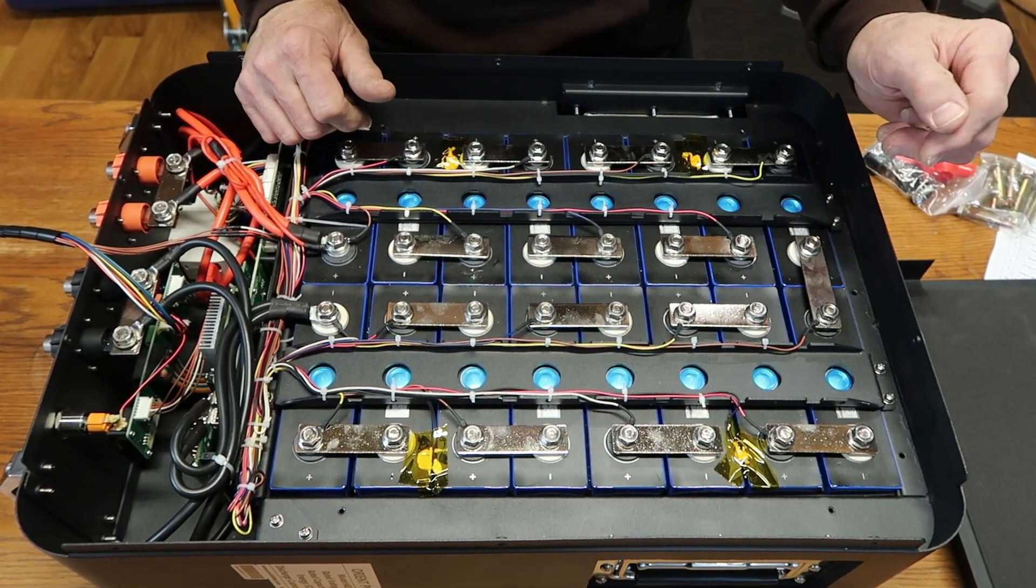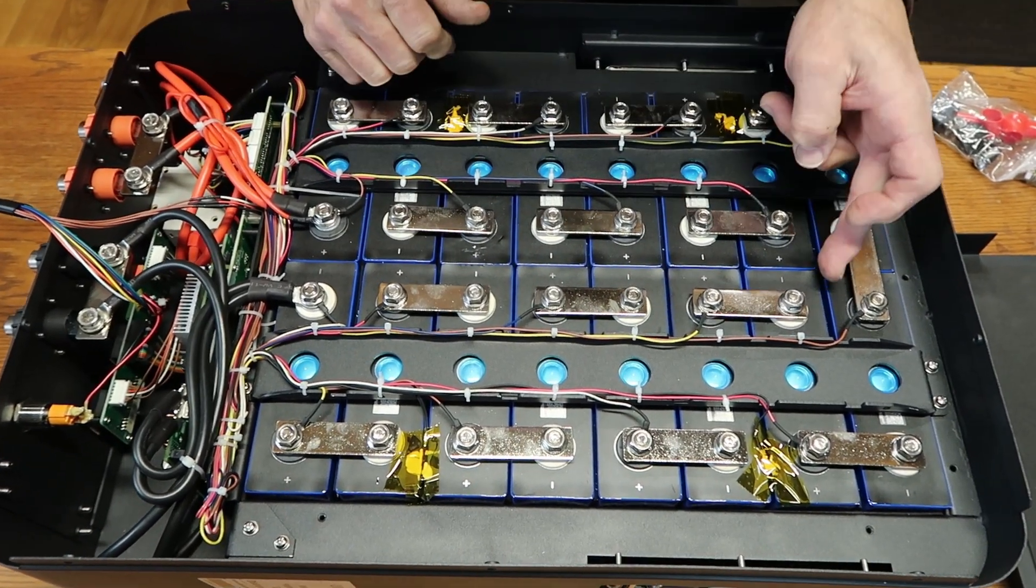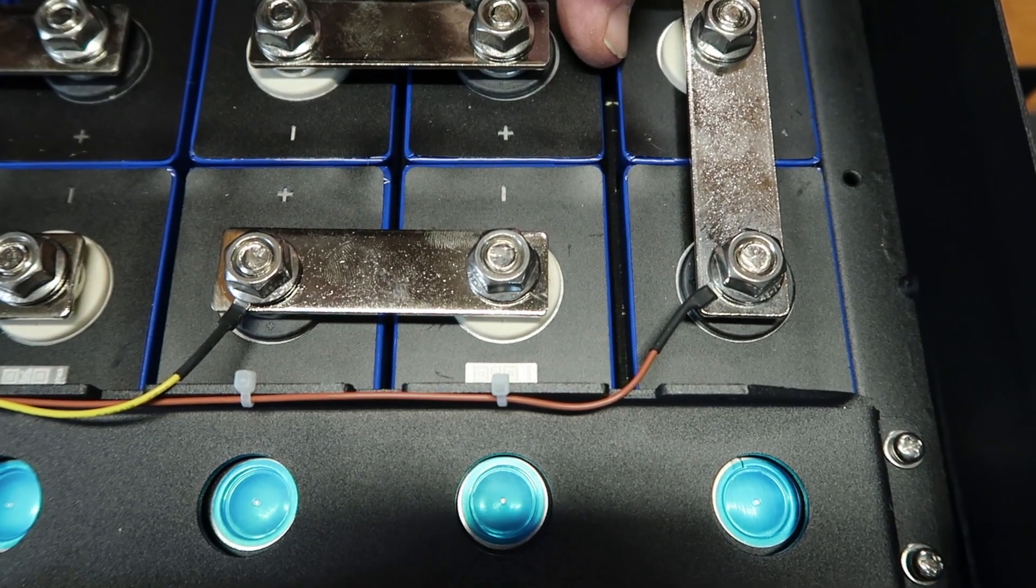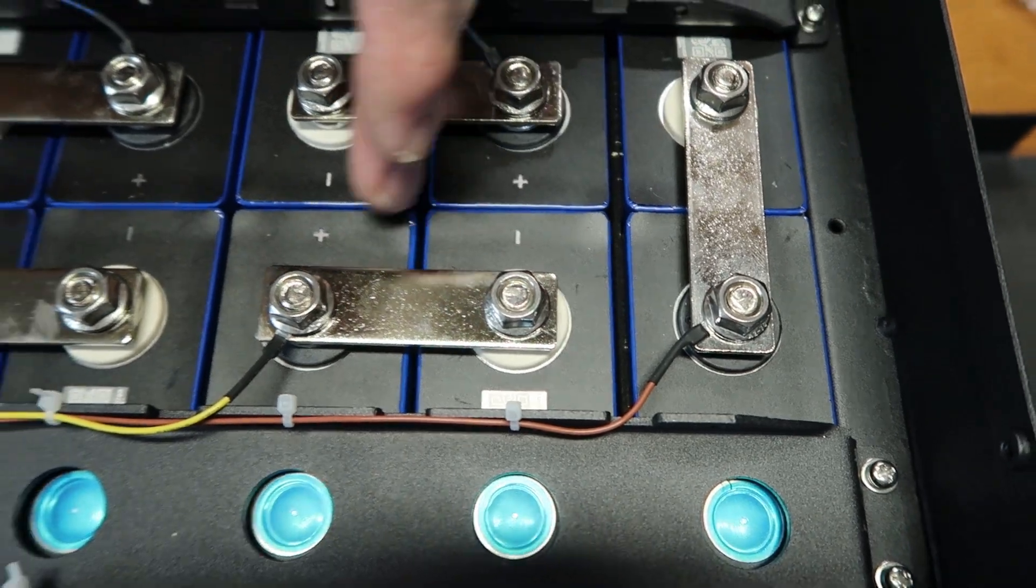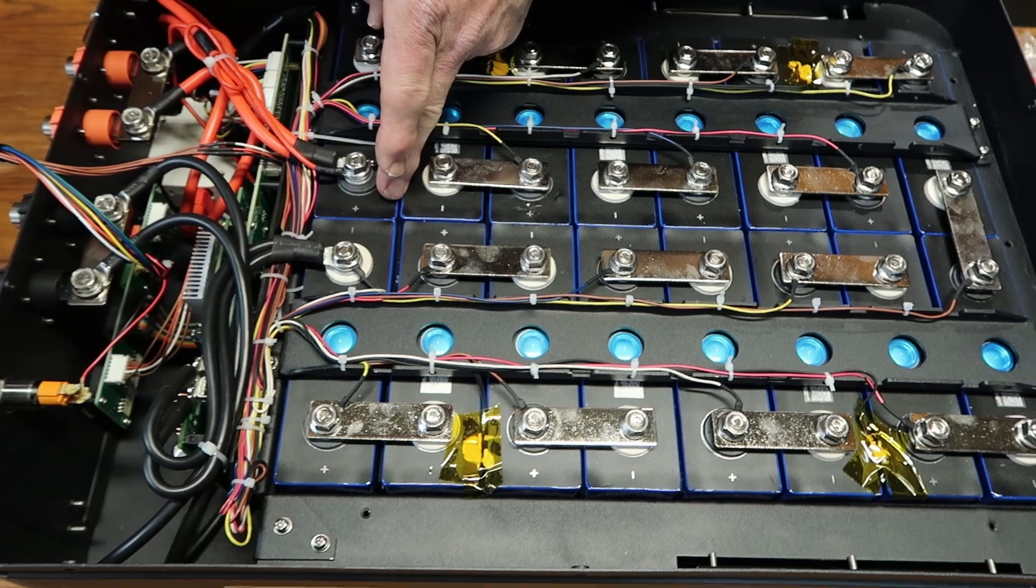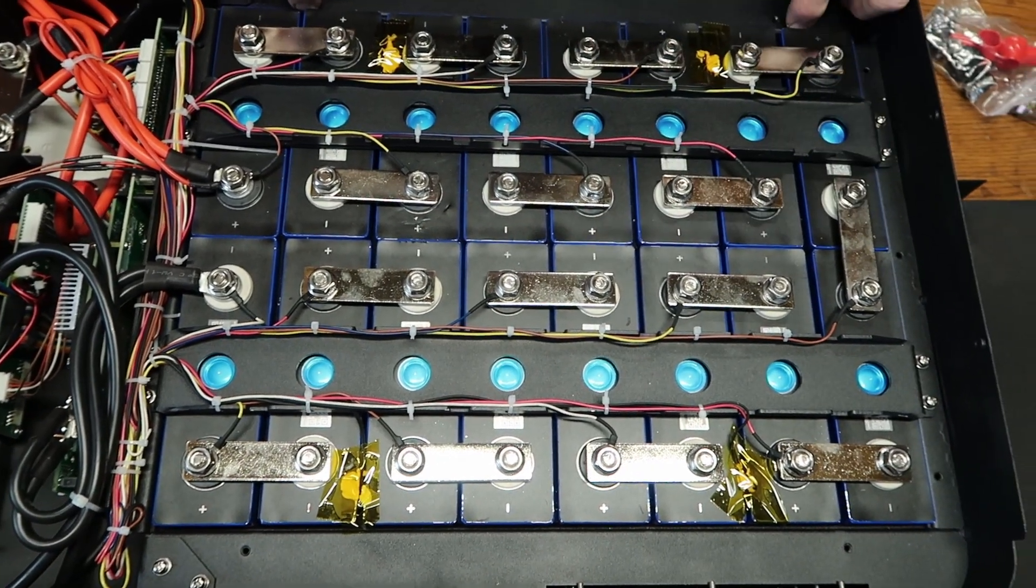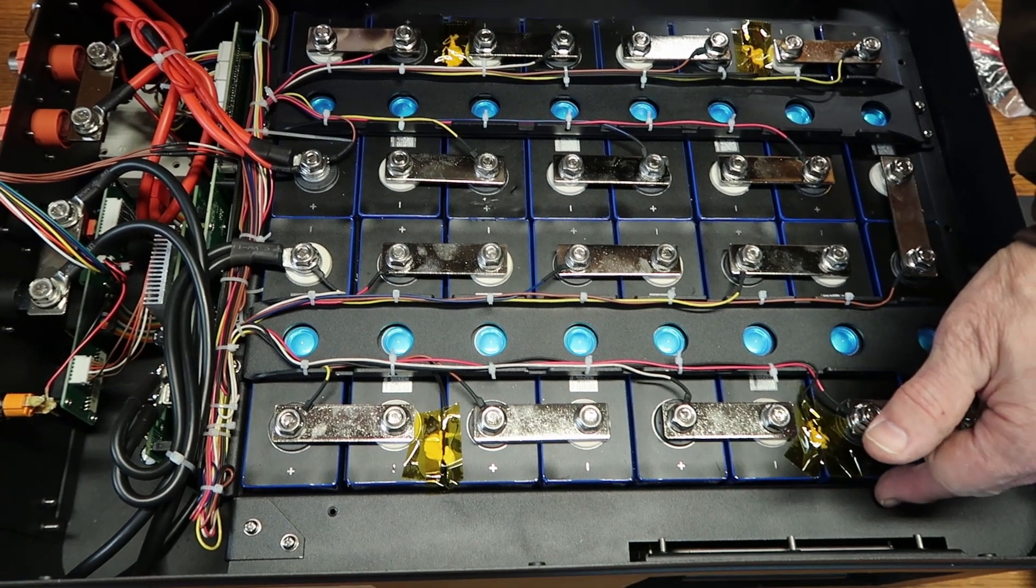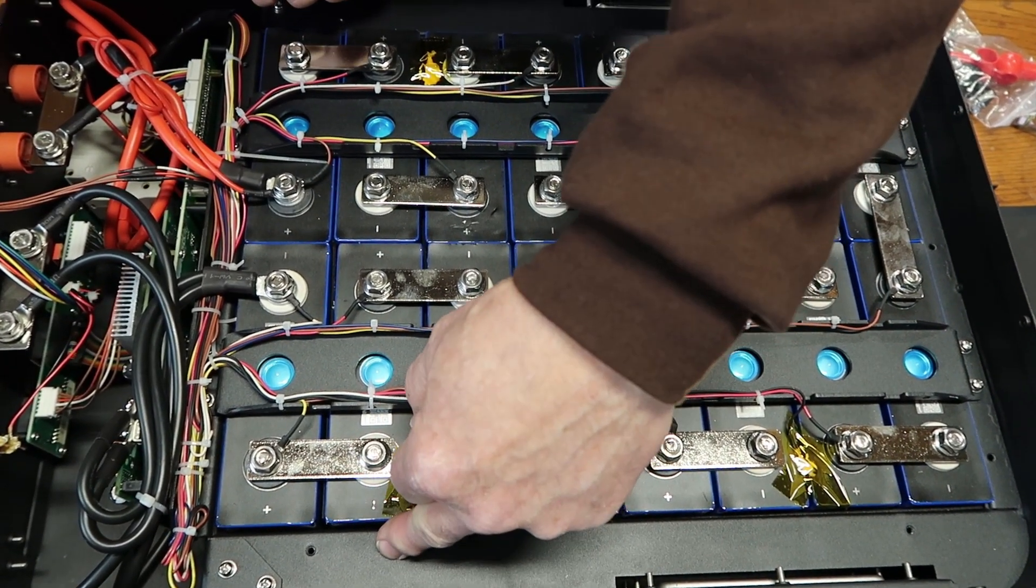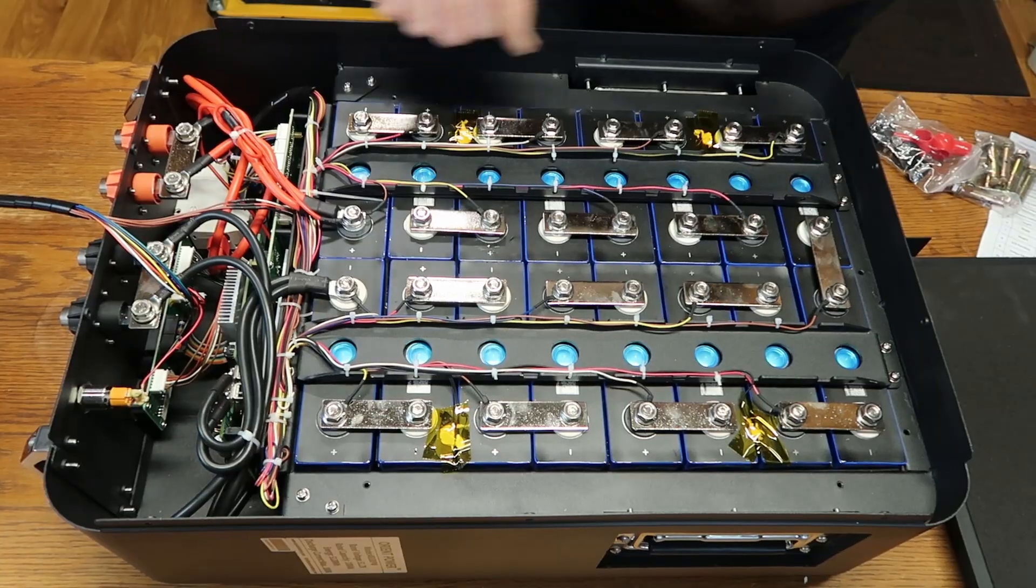We did notice that probably to help from any kind of rubbing with any expansion on the cells, in between these rows we do find the tape foam that they usually tape onto the sides. Each one we did check down, they all have the tape. There is foam along the side. So we're protected along the sides from this metal, which I'm pretty sure has a non-conductive coating. That's something we will have to remember to check next time.